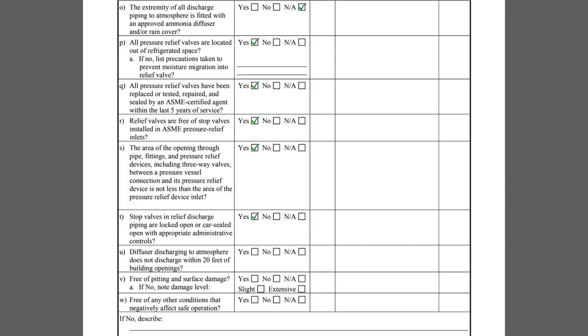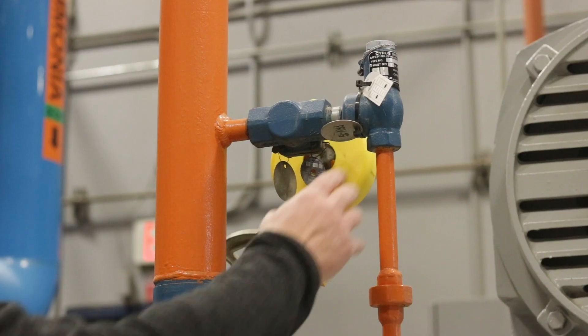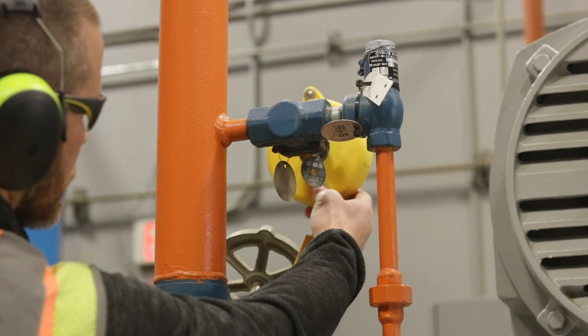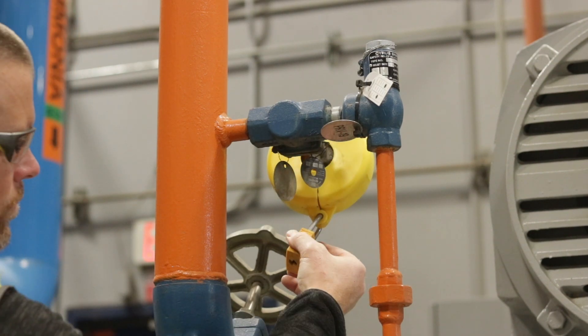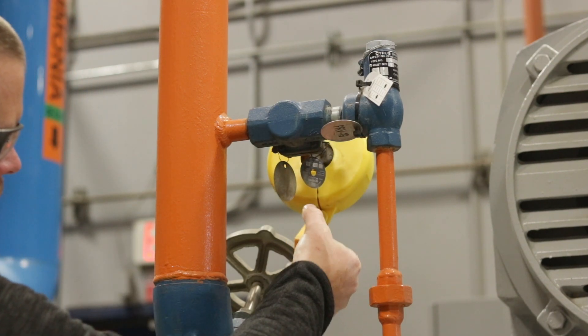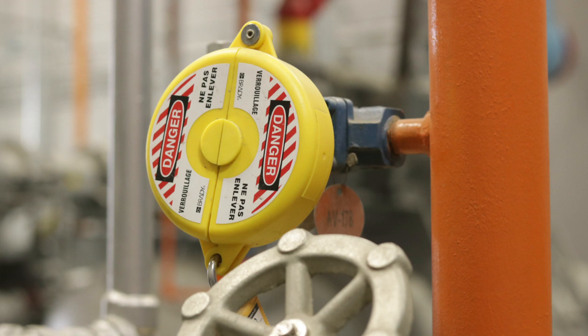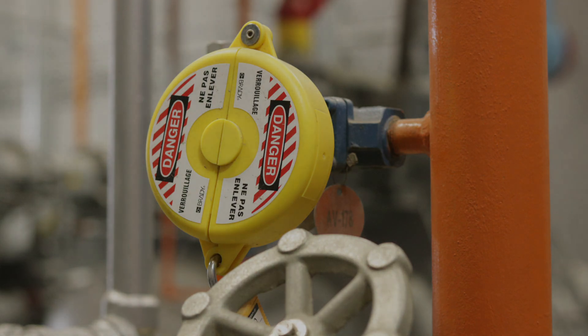Item T asks if stop valves in relief valve discharge piping are locked open or car-sealed open with appropriate administrative controls. This oil cooler relief valve terminates back into the system and has an outlet isolation valve that is locked open as required.